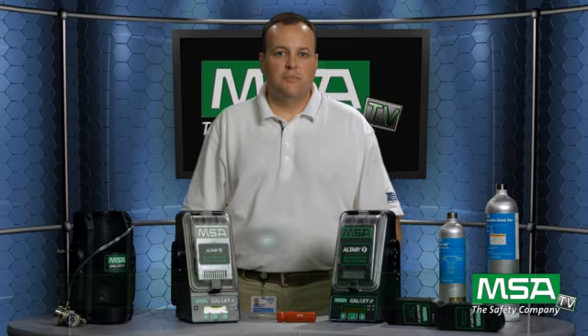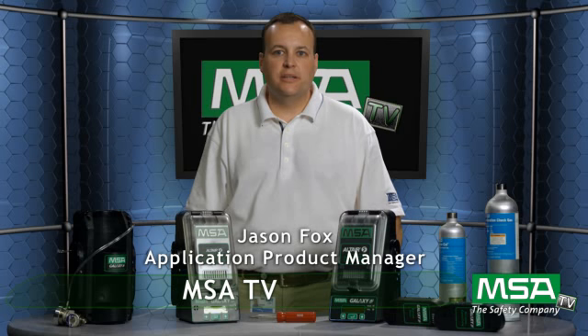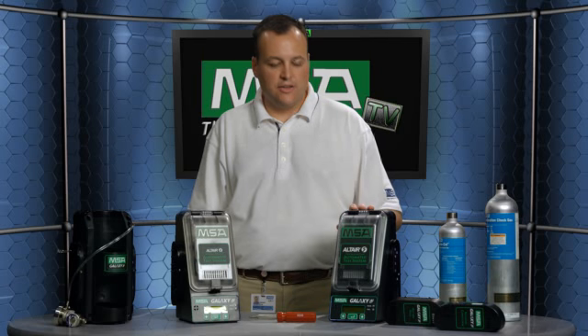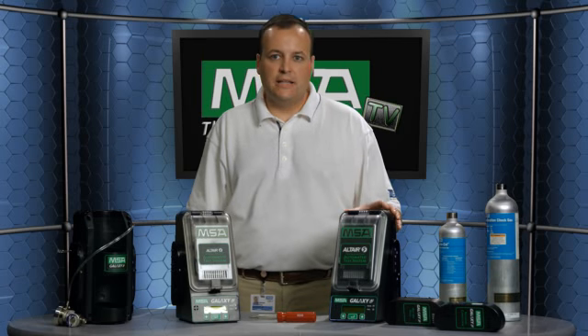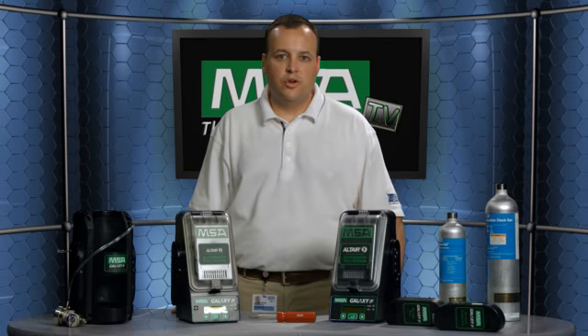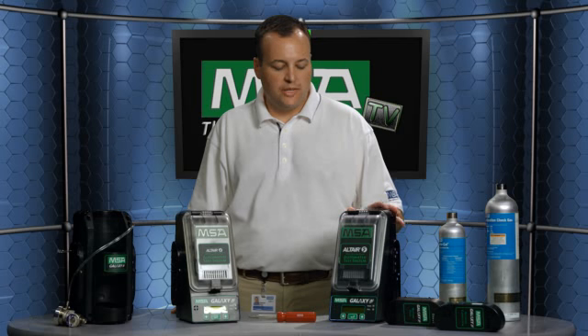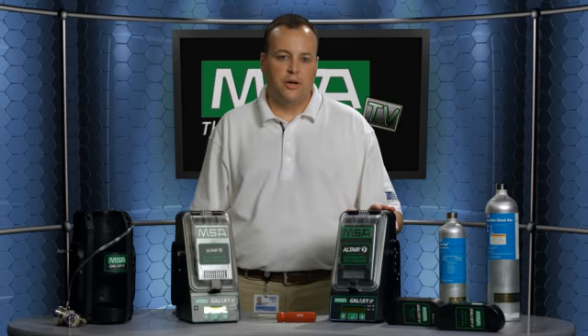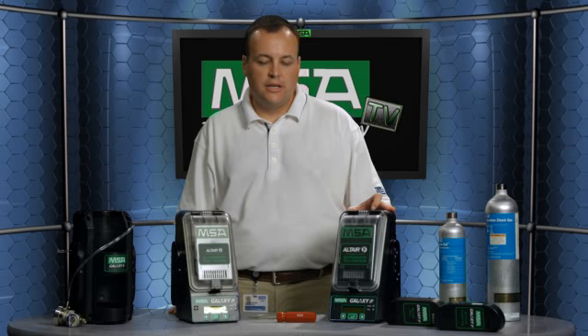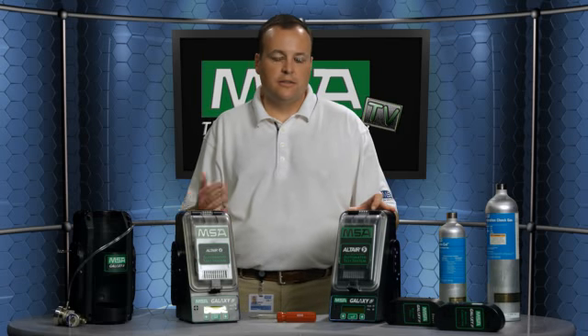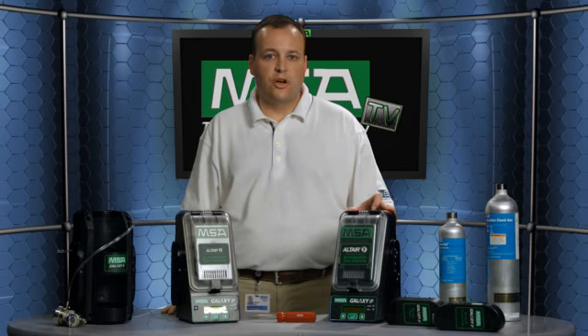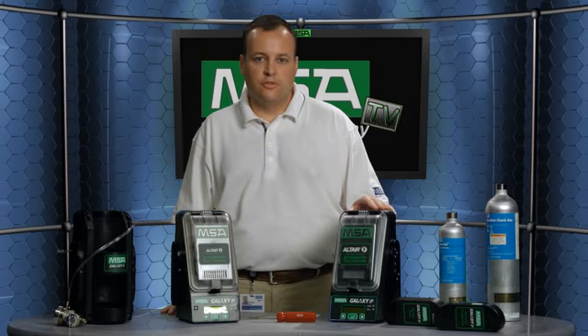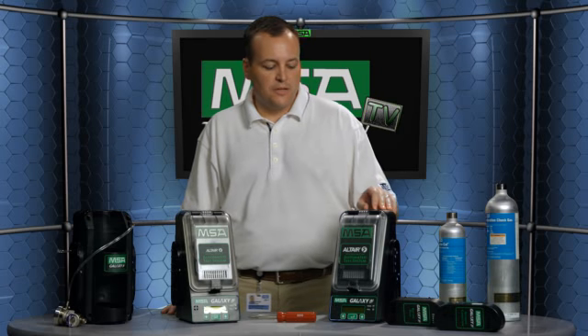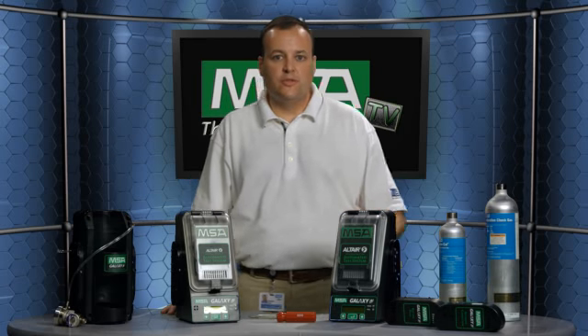My name is Jason Fox and I'm the product line manager for portable gas detection here at MSA. I handle single gas detectors and also the Galaxy automated calibration system. The Galaxy calibration system is what I'm going to talk to you about today, and it is a very nice all-in-one package that makes it convenient for the end user to do an automated calibration or bump of their portable gas instruments, and then also to maintain a record of that either by print or electronically through different memory devices. The system is very easy to use and very easy to set up.